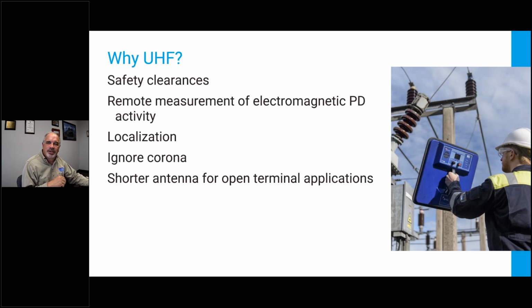UHF, I touched on this a little bit. Radio waves are great. Radio waves come out of sparks. It's just part of the nature of the physics. If I can get out there with a piece of test gear and measure that, I can see stuff that might be internal. If I had PD inside this bushing, which is very common, it's inside, so I'm not going to create ultrasonic. It's not inside a metal box, so I can't use TEV. It's not necessarily going directly to ground, so a ground strap isn't going to help me very much with an RFCT. UHF is my best way to go.